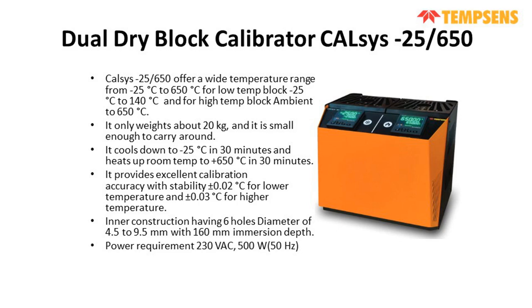Then we have dual dry block calibrators. So two dry blocks are comprised in a single body. One dry block has a temperature range of minus 25 to 140 degrees, and the other has ambient to 650 degrees. So we can say the temperature range is minus 25 to 650 degrees, and the weight of this calibrator is just 20 kgs, and it is small enough to carry for on-field applications also. It cools down to minus 25 degrees in just 30 minutes and heats up from room temperature to 650 in 30 minutes. It has a stability of plus minus 0.02 for the lower temperature and plus minus 0.03 for the higher temperature. And for insert construction, again we have 6 holes with diameters of 4.5 to 9.5, and we can customize it. The immersion depth is 160 mm, and the power requirement is also low, it takes 500 watts.